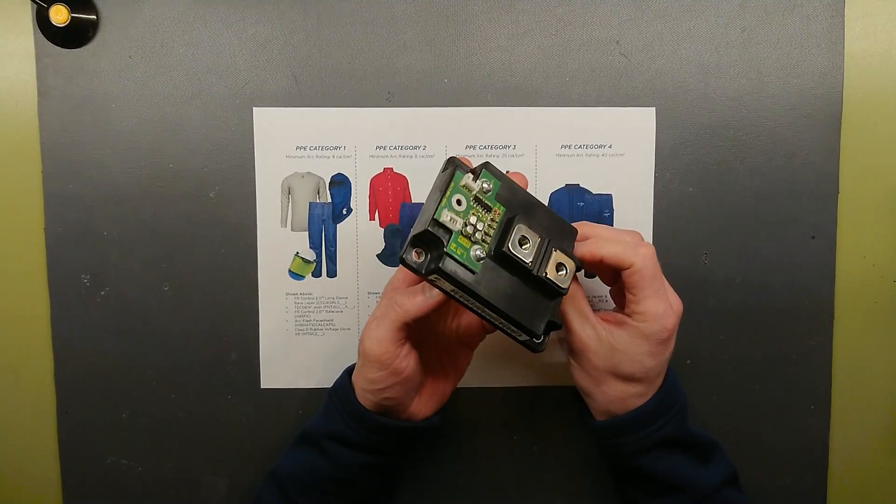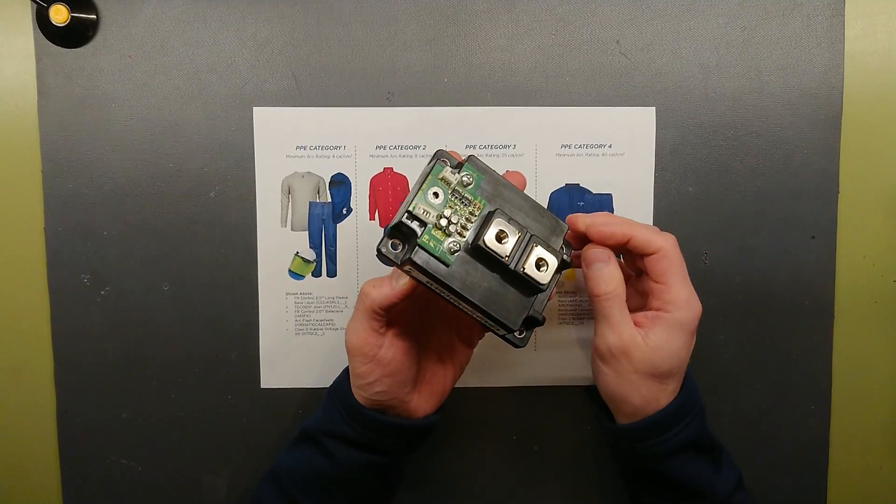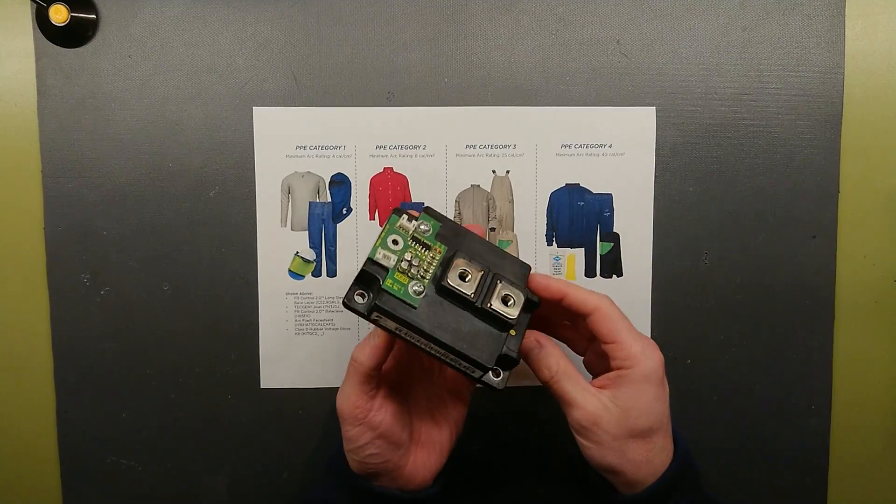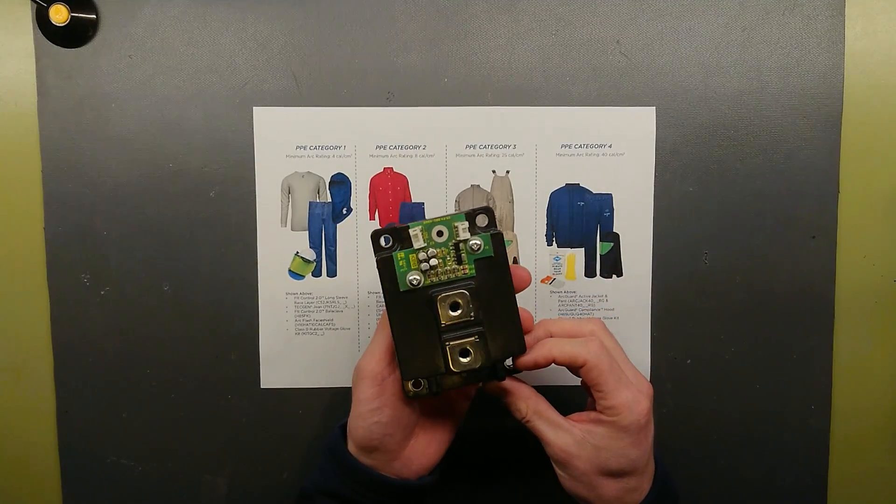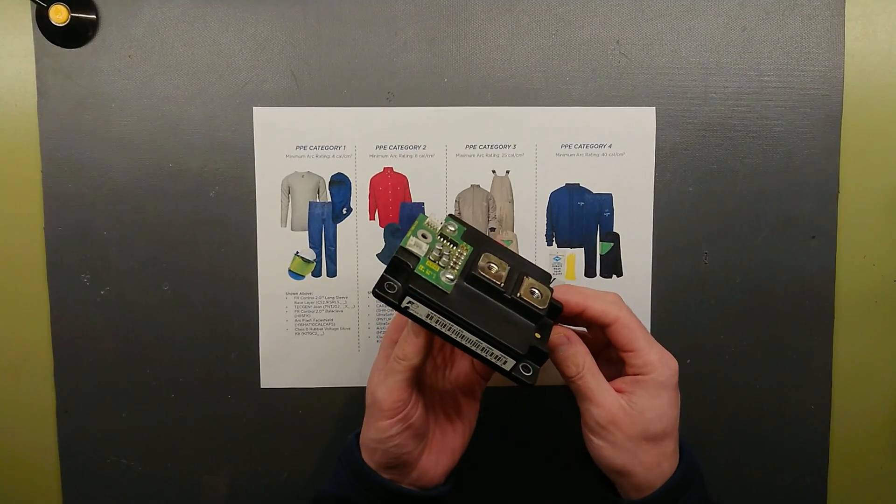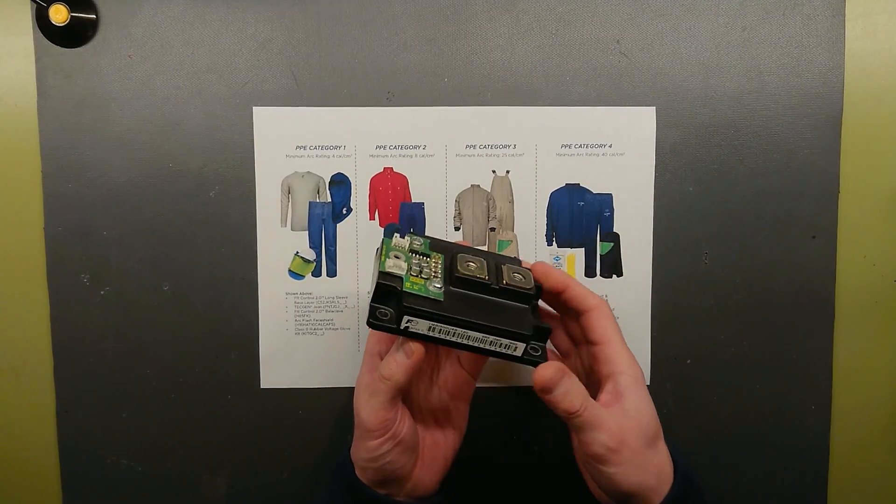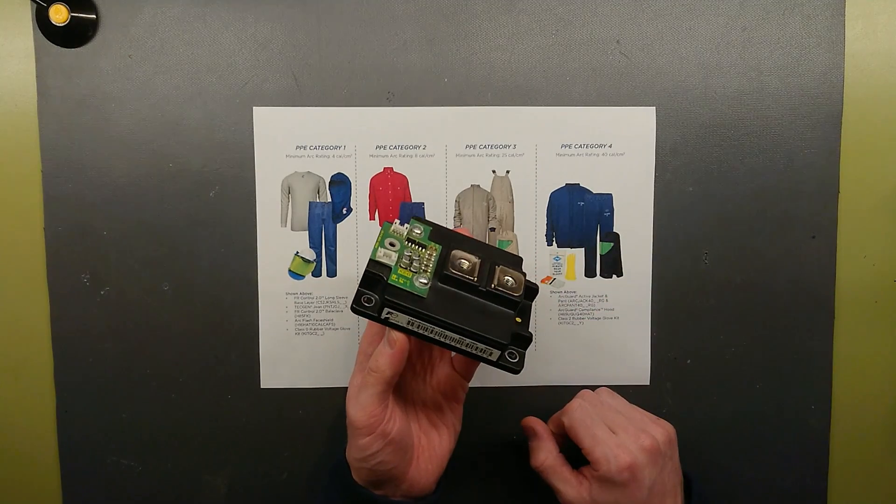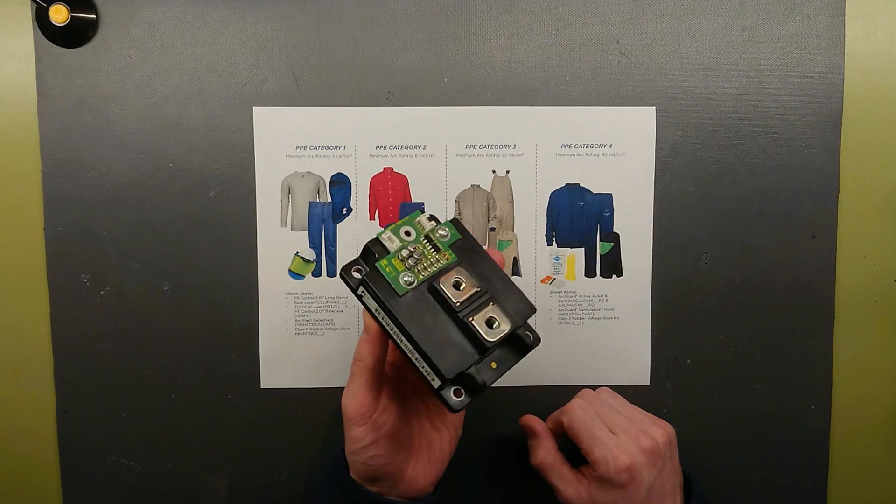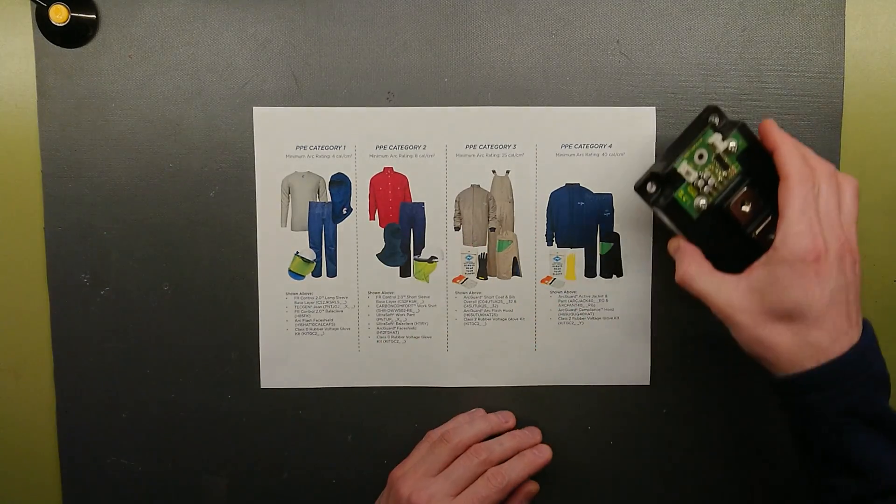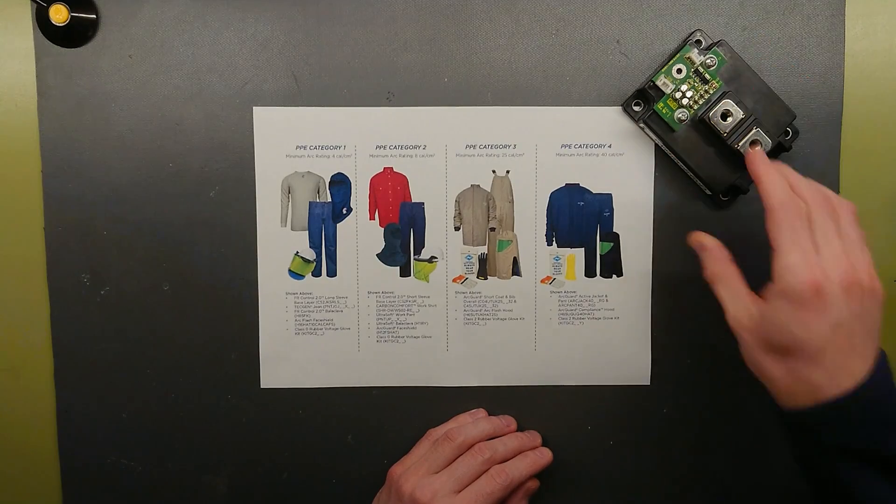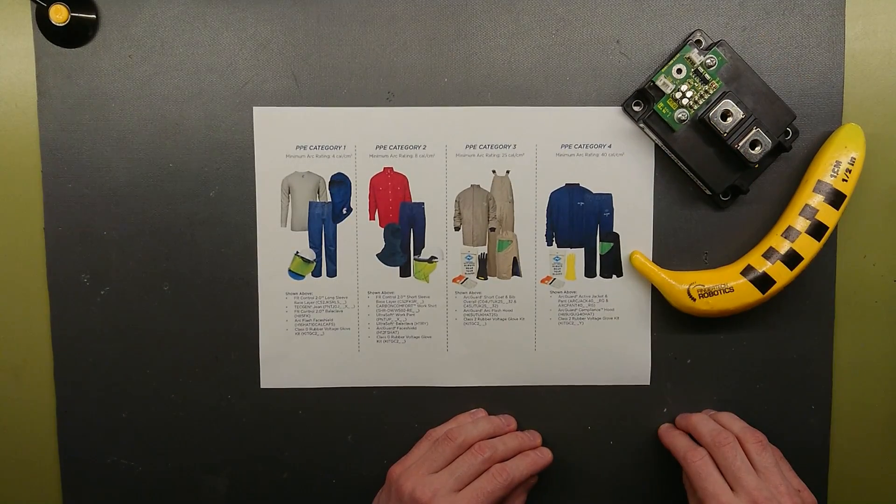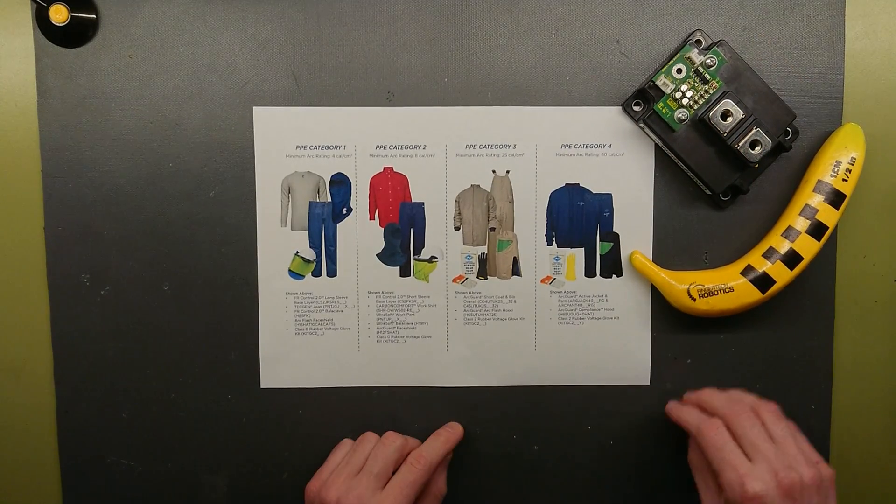If you blow them up from letting through too much energy at a short circuit fault. These can withstand a quite substantial amount of energy due to their thermal mass. But if it is exceeded its rating, it is usually in the datasheet that these are rated for an X amount of short circuit current for one millisecond. You just size your fast acting fuse to this.